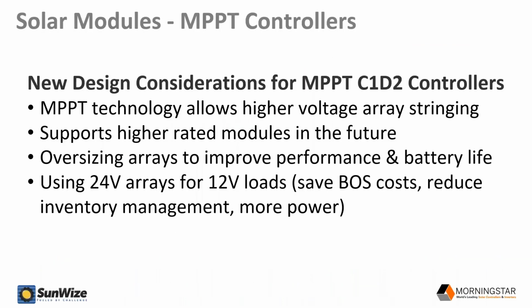So some of the design considerations that we want to be thinking about when it comes to solar modules and array, now that we have MPPT and C1D2 charge controllers, is the fact that the MPPT technology in these base devices allows for higher voltage array stringing due to that maximum open circuit voltage on the charge controller. It also is going to future-proof some of your designs a little bit by supporting in the future these higher rated capacity solar modules, which are always growing in size due to cell efficiency increases in the marketplace and from manufacturers.